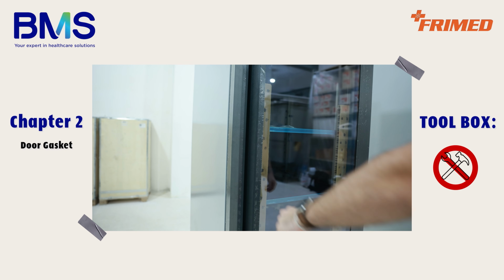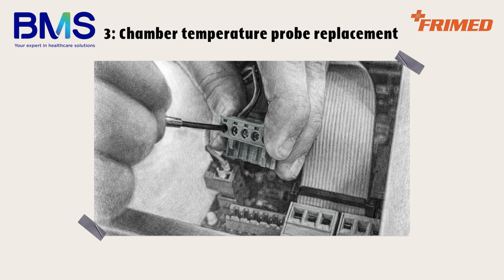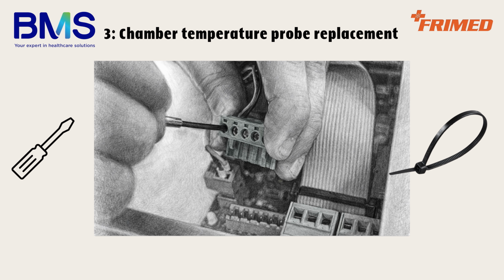No tools are needed. Replacing the chamber temperature probe is essential to ensure accurate temperature monitoring and control. A faulty probe can cause incorrect readings and undetected temperature deviations, putting stored products at risk and compromising cold chain compliance. The process is straightforward and requires minimal tools: one screwdriver and one plastic strip.